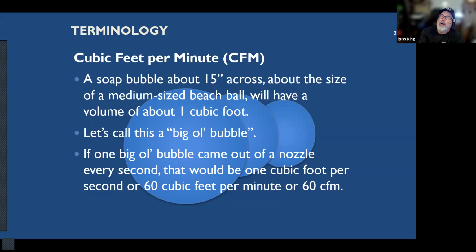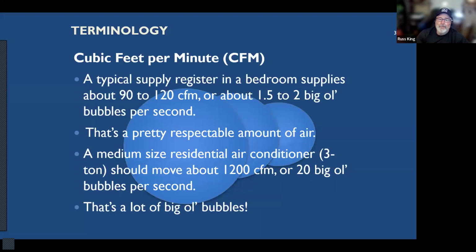60 CFM is about how much air you would blow into a large bathroom to heat it and cool it. A typical bedroom in a house, depending on the climate and the size of the ducts, you'd blow about 100 CFM, maybe 120, 130 CFM, cubic feet per minute, so 130 bubbles per minute coming out.